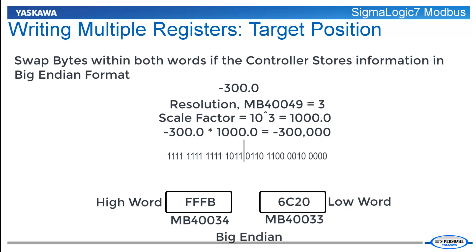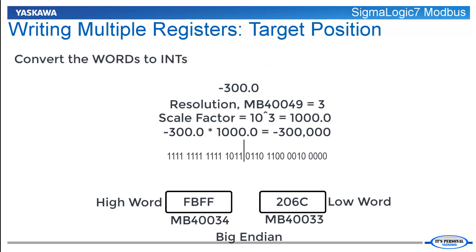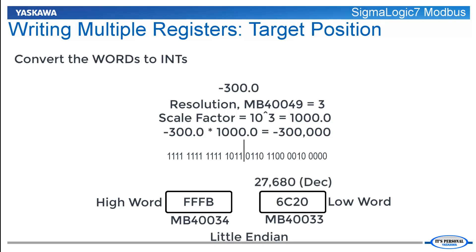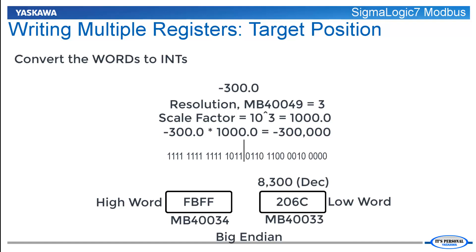If the controller stores data in big-endian format, swap the bytes within both words. This will result in the low word changing to 206C and the high word changing to FBFF. Finally, ensure the data type of the final values placed in the registers is expressed as an integer. If stored in little-endian, the low word 6C20 hex equals 27,680 decimal and the high word FFFB hex equals negative 5 decimal. If stored in big-endian, the low word 206C hex equals 8,300 decimal and the high word FBFF hex equals negative 1,025 decimal.